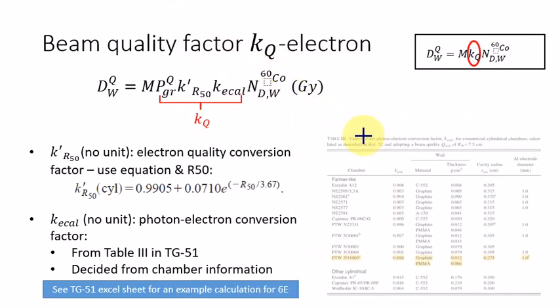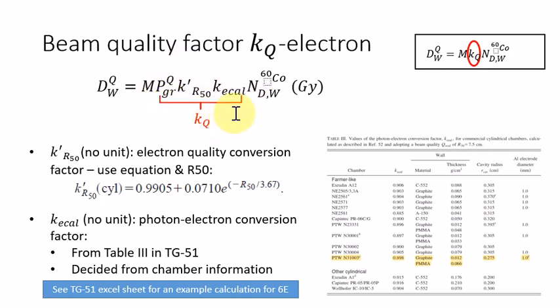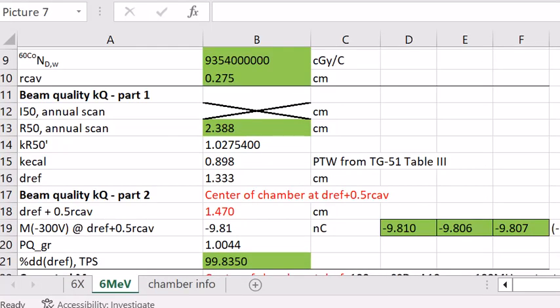So this is the breakdown of the KQ factor for electron beam — it's the multiplication of these three factors. Two of these factors will need the R50 value and the DREF. Let's see an example sheet for a calculation of the 6 MEV electron beam.